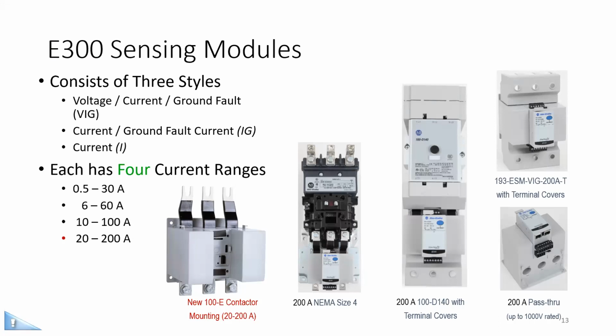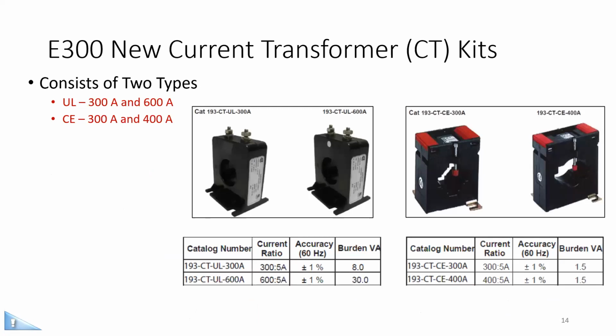And there are 4 different current ranges. So we've got 0.5 to 30 amp, 6 to 60 amp, 10 to 100 amp, and 20 to 200 amp. All 12 of the sensing modules can mount 100C, E, and some older 100D contactors if you still have them. Bulletin 300, 500 NEMA contactors, and most can be DIN rail or panel mounted. For amperages over 200 amp, we do have current transformer kits available. You see the different ones that get you different ratios to get you kind of where you need to be. We offer these with UL markings, and then there's some with CL, CE as well.